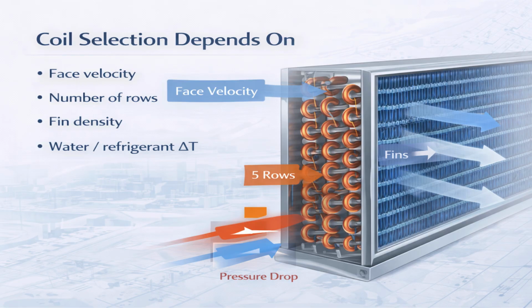Coil selection is often misunderstood as simply choosing the number of rows. In reality, it is one of the most critical and most sensitive parts of HVAC unit selection. A coil's real performance depends on several interacting factors. The face velocity of air across a coil, fin spacing and fin density, the number of coil rows, the refrigerant or chilled water temperature difference, and the allowable pressure drop through the coil.